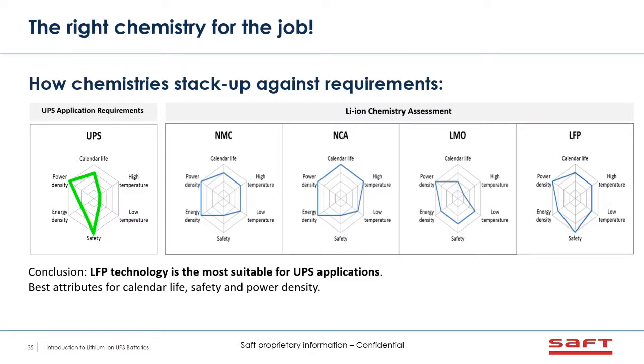Looking at how we designed the battery system from a chemistry point of view, we looked at the application requirements and graded what a UPS needs. We determined that calendar life, power density, and safety were the key requirements for the UPS application, and based on that, LFP provides zero trade-offs on those attributes, so we chose an LFP-based chemistry to start our Flexion design system.